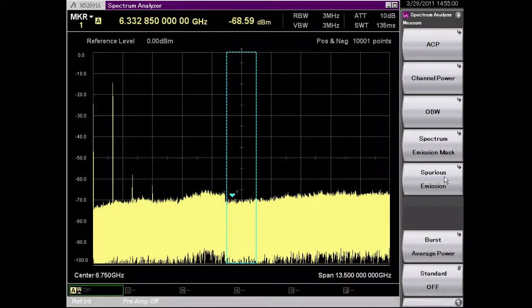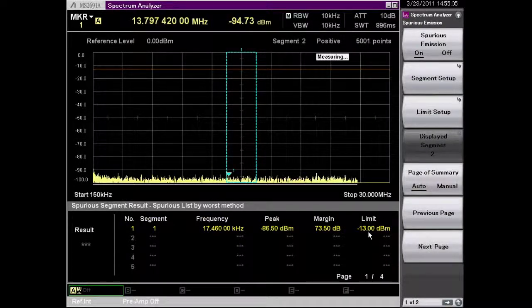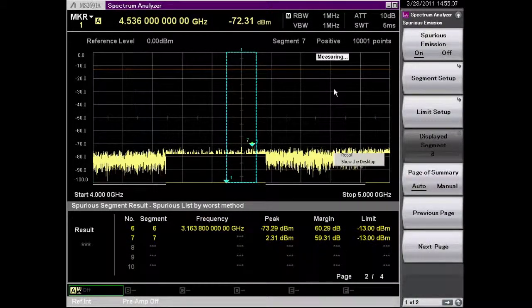Under Measure I have Spurious Emission. I will select that. Now when running Spurious Emission it's probably best to do a single sweep.